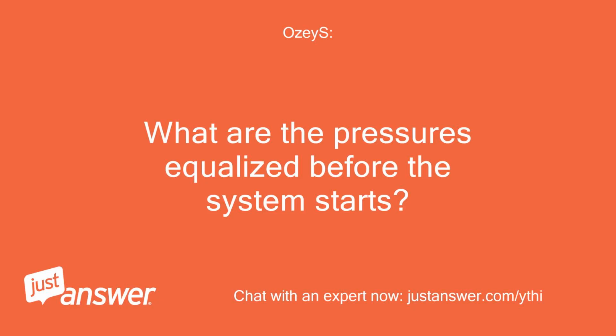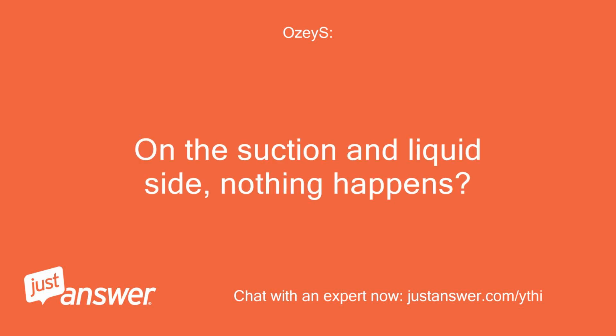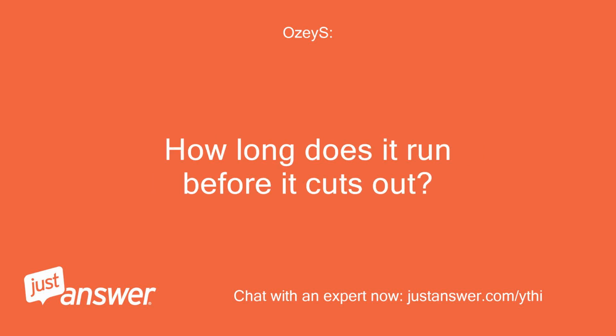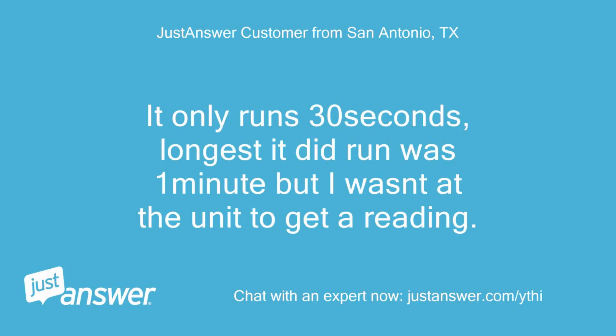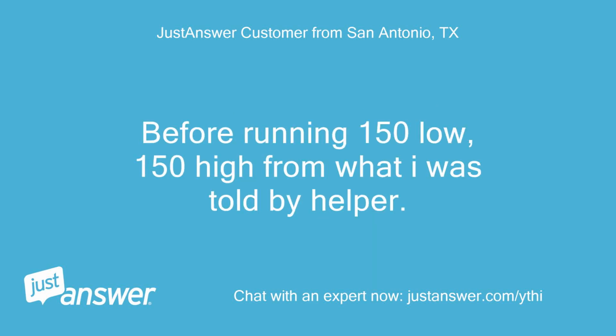Are the pressures equalized before the system starts? On the suction and liquid side, nothing happens? How long does it run before it cuts out? It only runs 30 seconds, longest it did run was 1 minute but I wasn't at the unit to get a reading. Before running 150 low, 150 high from what I was told by helper.